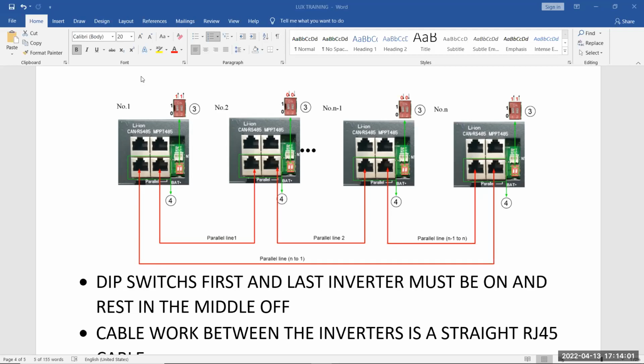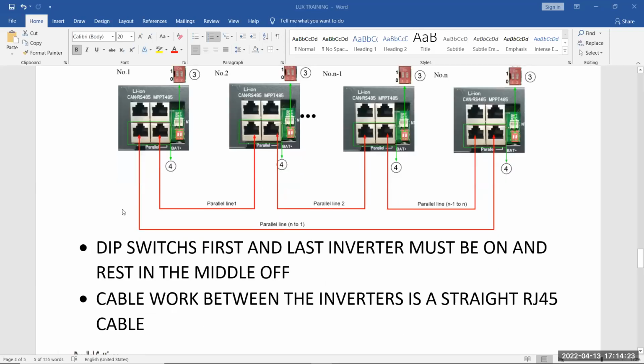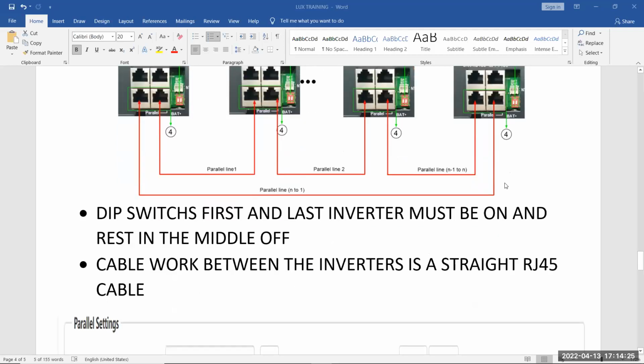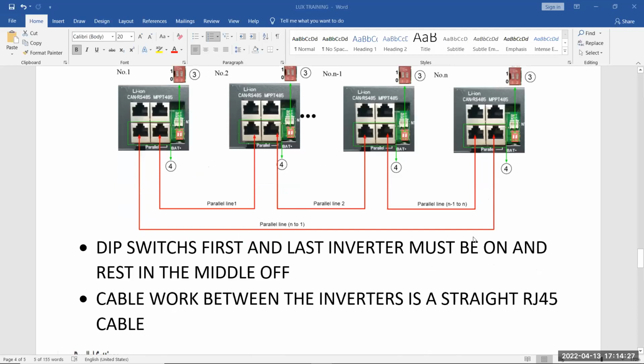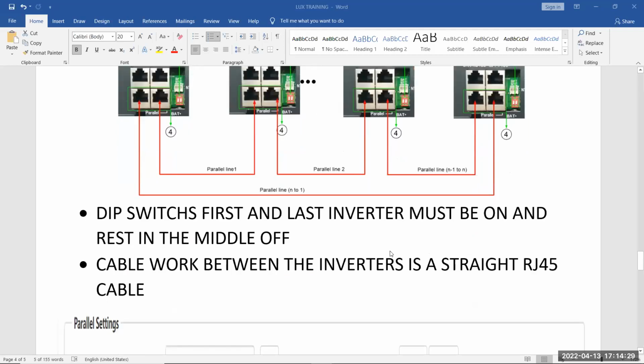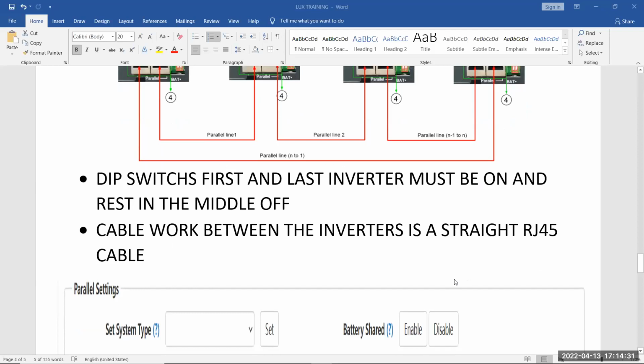So in a system that's only 2 inverters, it's up, up. If there are 3 or 4 inverters, you'll see the first one will be up, the second one will be down, and the fourth one will be up again. That's basically my parallel settings on the inverters themselves without doing the settings on the screen. Dip switches, as I said, the last one's on, and then the middle one's off. Cable work between them is a straight RJ45 cable.